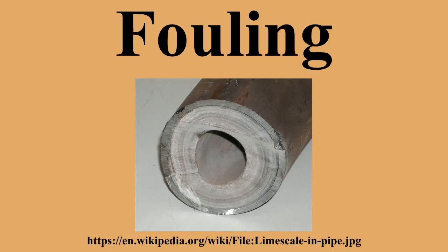Negative fouling. This can occur when fouling rate is quantified by monitoring heat transfer. Relatively small amounts of deposit can improve heat transfer relative to clean surface, and give an appearance of negative fouling rate and negative total fouling amount. Negative fouling is often observed under nucleate boiling heat transfer conditions or forced convection. After the initial period of surface roughness control, the fouling rate usually becomes strongly positive.